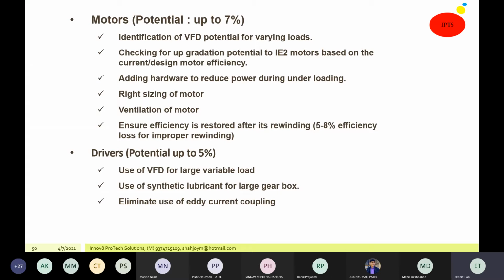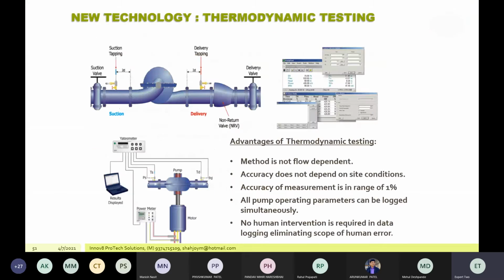New technology. Say now, several pumps: what is the efficiency? It is very difficult to measure. So new technology like thermodynamic testing is available. We use this testing in large pumps and identify what the efficiency is and the improvement possibility of the efficiency. Some opportunities in the fans and blowers. Several fans and blowers are used in several industries. So VFD is one of the options available for variable speed.